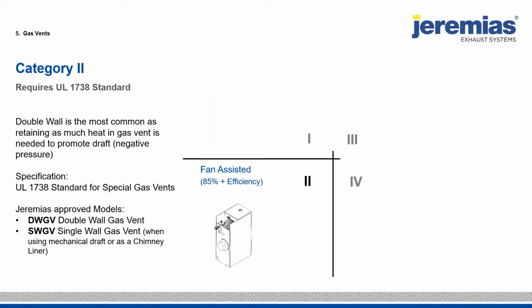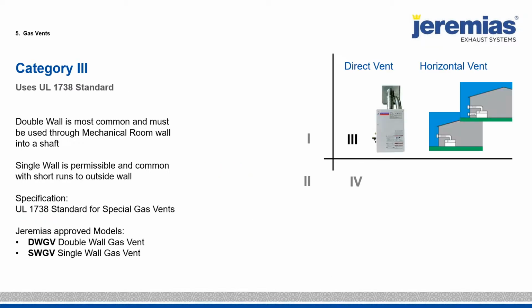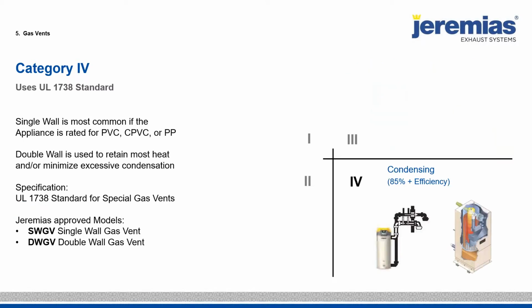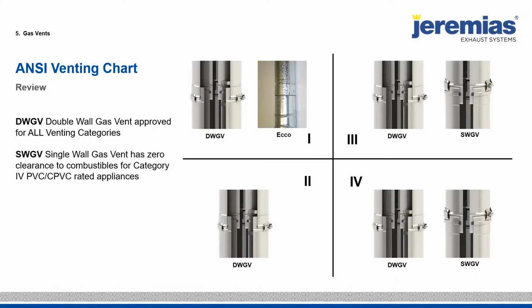Category 2 is when we move into a new standard, UL 1738. So typically the requirement is our single and double wall special gas vent. Category 3 remains that UL 1738 special gas vent. And category 4 again remains that UL 1738, or it could be approved for maybe PVC or CPVC or polypropylene. So just a quick review. Again, our DW double wall gas vent is good for all categories. And then type B gas vent is only good for category 1.